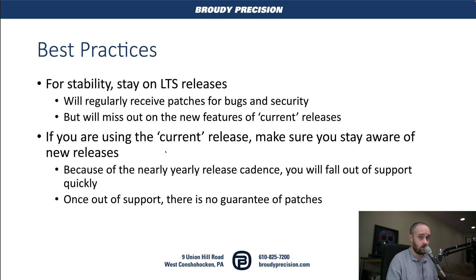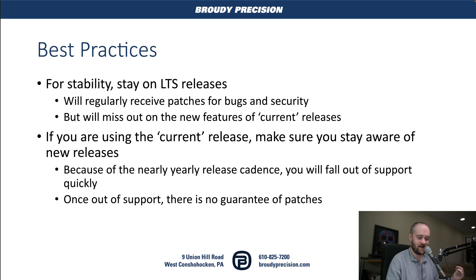If you are staying on a current release because you want those new features, or there is a specific feature you want in a current release, it's important that you keep aware of when new releases are published by Tridium. Because with the cadence they're following now, no matter when you install a version that's current, you'll probably fall out of support within a year. In our support channel at Brody, it's not uncommon for us to get emails on support for versions of Niagara that have been fairly long out of support. If you stay at the LTS release, the likelihood of that happening is significantly less, because you have way more time to stay there and your bug fixes — since they're just modules — are much quicker to install than a full major release upgrade.